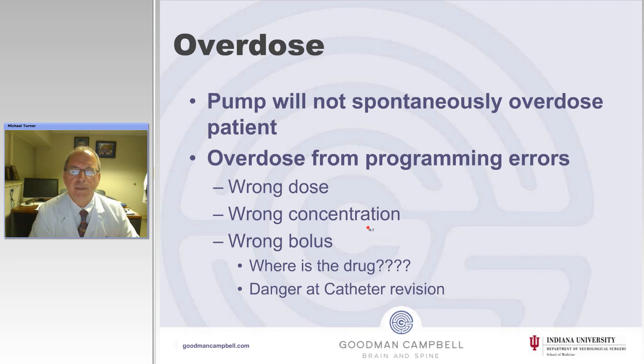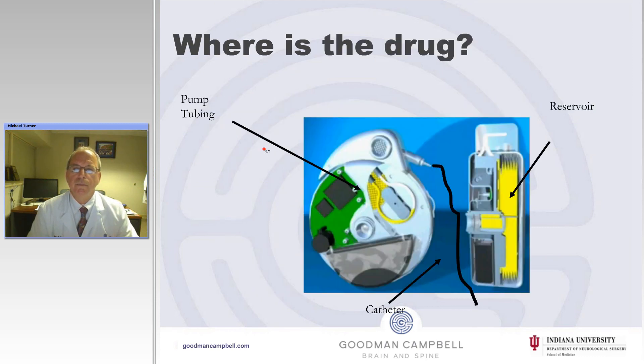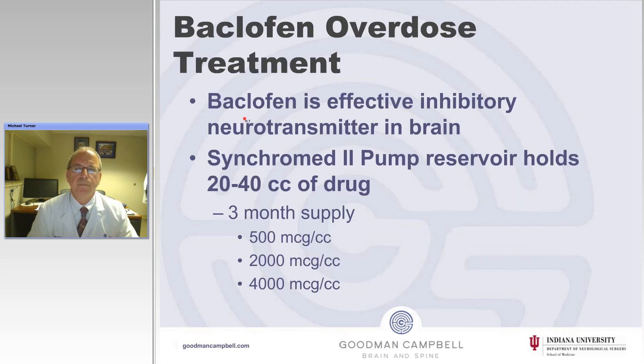Where is the drug is a big concern, and there is a danger of overdose with catheter revisions. A drug can be in the reservoir, in the internal pump tubing, or in the catheter.